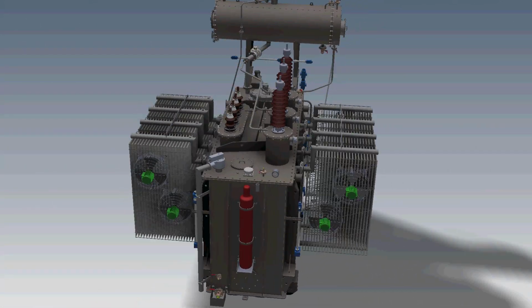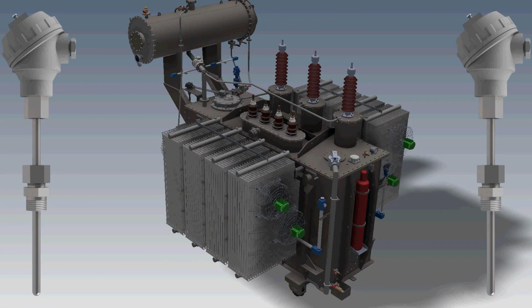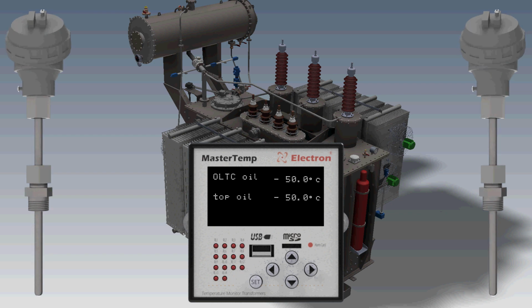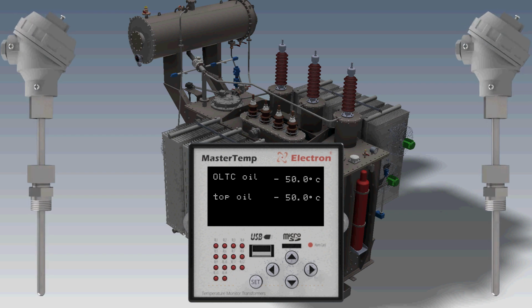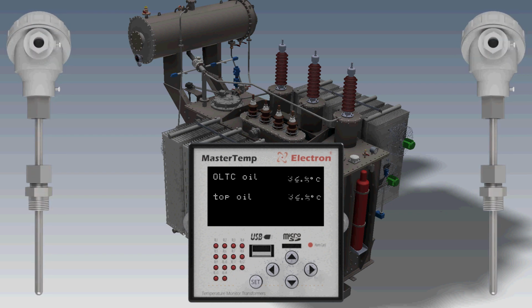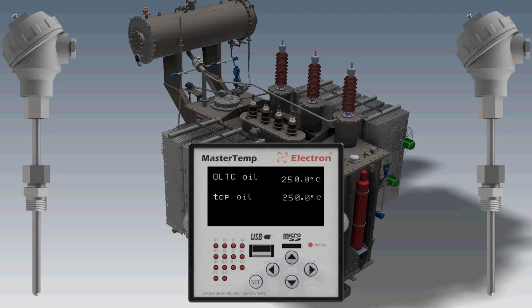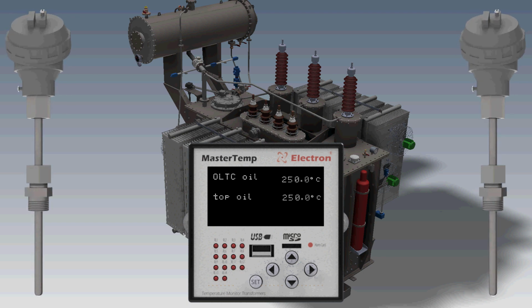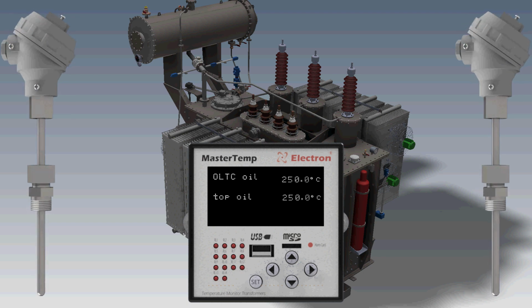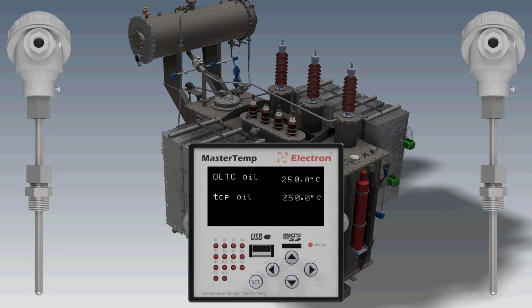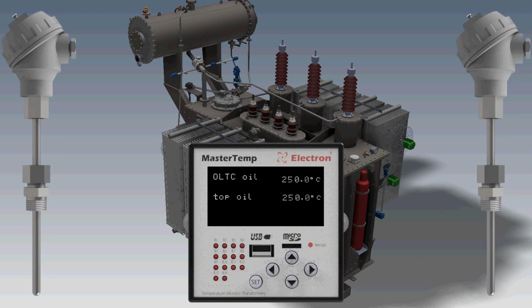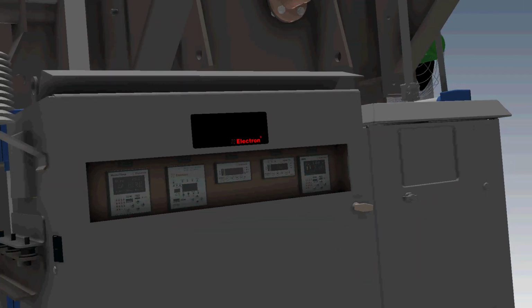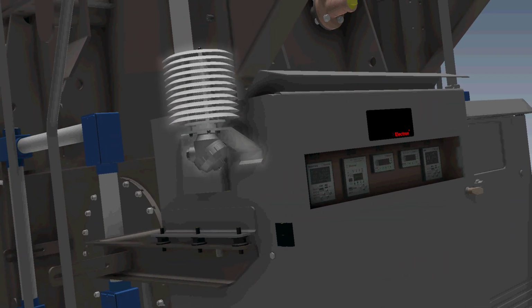The oil temperature monitoring is done through up to 2 PT100 sensor type, with measuring range between -50 degrees Celsius up to 250 degrees Celsius with 0.25% precision. The indication is done with a decimal place resolution. One of the sensors can also be used for environment temperature acquisition, for use in calculating permissible loading of the transformer.